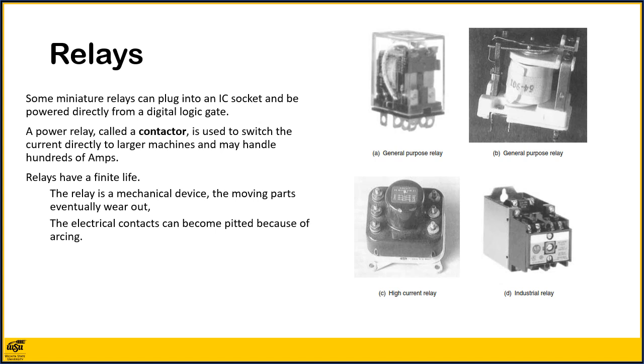Contact life is also dependent on the type of load being controlled. For example, inductive loads such as motors cause much more arcing and pitting than resistive loads such as lights and heating elements.